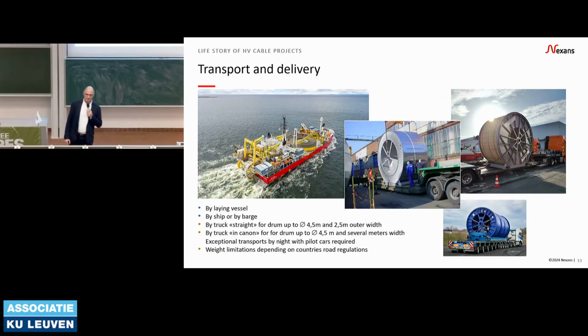Then you have to transport it. Your project is still not on site. It's produced, but then you have to move it. You can move it for the land cable mostly by truck. This is the most common manner we use to move the drums, because the size is not that big, even though some drums can have up to 6 meters width, because the diameter is blocked by road limits or weights. So depending on the type of cable and the maximum length we want to put on the truck, we will go to longer or wider drums, because the diameter is blocked to 4.5 meters.